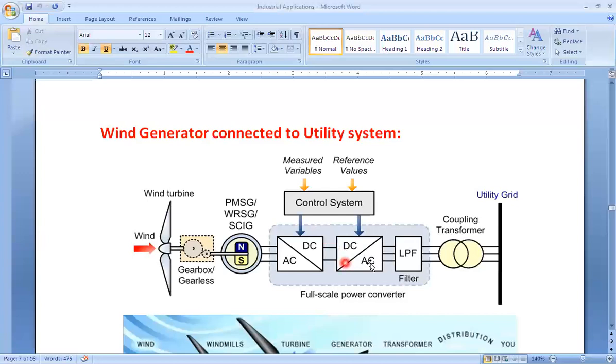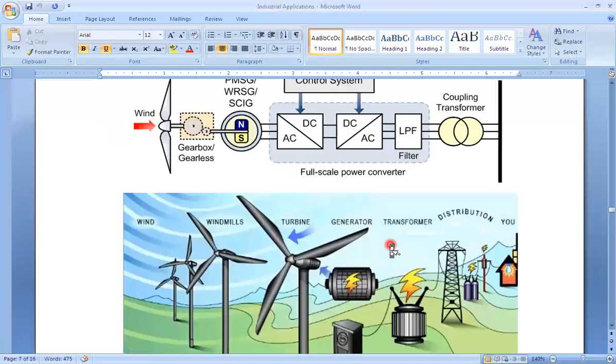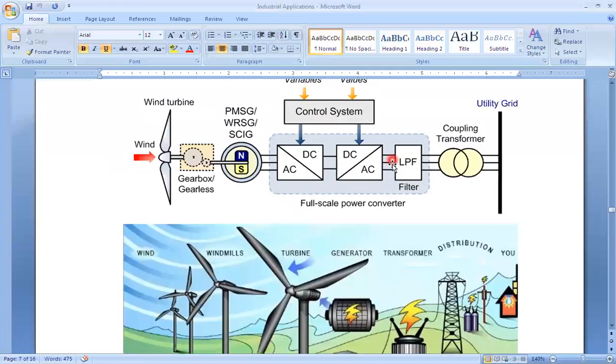So this is our DC to AC converter, that is called the inverter. The input to this inverter is a DC input, and this DC input will be converted into AC by controlling the proper parameters, generally the frequency as well as the voltage. If you want the 50 hertz frequency, then trigger this inverter according to that 50 hertz frequency. Then at the output of this inverter, you will again get three phase with the 50 hertz frequency.